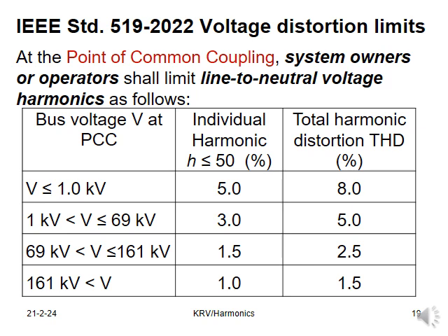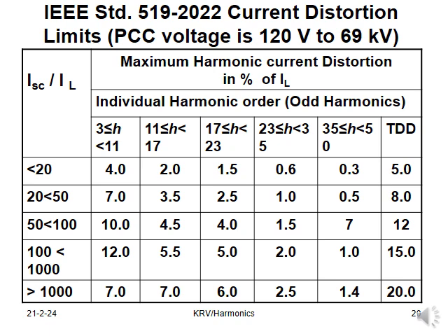As per the IEEE standard 519, the voltage distortion limits are given in this table. At the point of common coupling, system owners or operators shall limit line to neutral voltage harmonics as follows. These limits are based on the bus voltage at the PCC. The standard also gives the current distortion limits for many PCC voltages. So this table is for the PCC voltage of 120 V to 69 kV. These values are based on a parameter called short circuit ratio, which is ISC divided by IL.